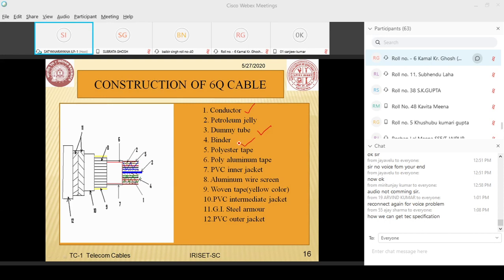Why is this binder tape required? This binder tape isolates the quads by virtue of its color code. Then comes polyester tape, poly-aluminium tape, PVC inner jacket, aluminum wire screen, woven tape again, PVC intermediate jacket, GI steel armor, and PVC outer jacket. This is the construction of the quad cable.